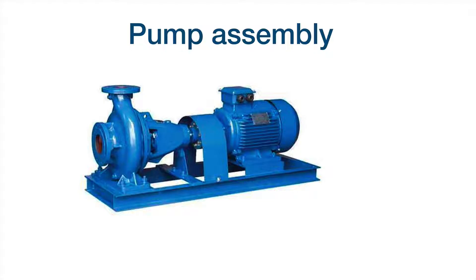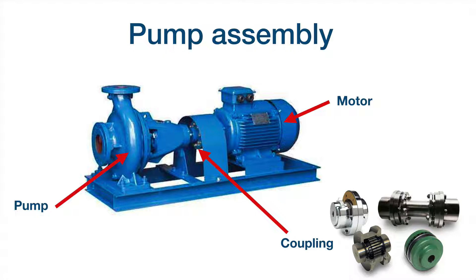Here we have a centrifugal pump driven by an electric motor. This is an end-suction type of pump, foot-mounted, because the supports are located at the foot of the pump. We also have the motor — as mentioned, an electrical motor. We can also have any other kind of driver such as a gas turbine, a steam turbine, or hydraulic drive. Here we have the coupling and the base plate, which supports both the pump and the driver.